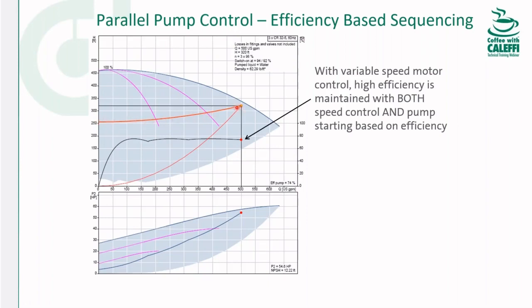And it's proportional. That's why it doesn't go straight across. Basically, at this head and flow, this is our efficiency, and at this head and flow, that's our efficiency. So the key here is that the controller is keeping the efficiency as high as possible. And we're at 75%+ pretty much for the whole flow range until we get down to maybe the bottom 20% of the flow range.